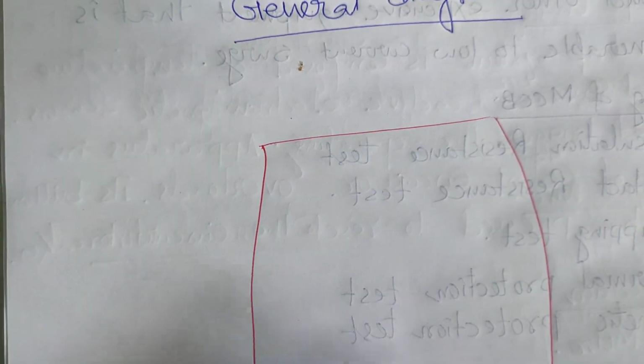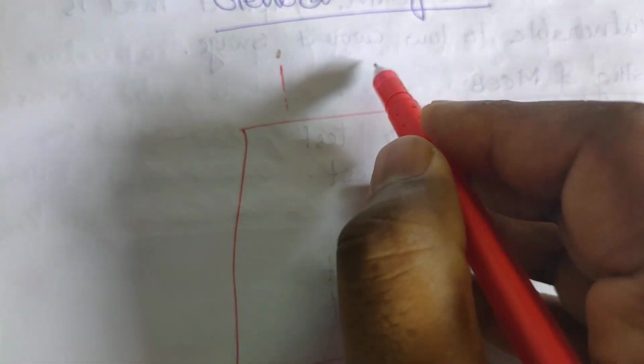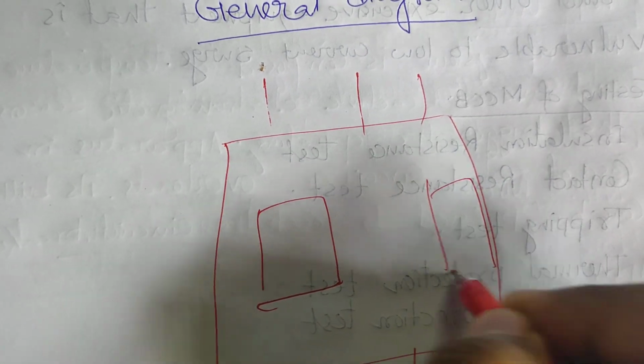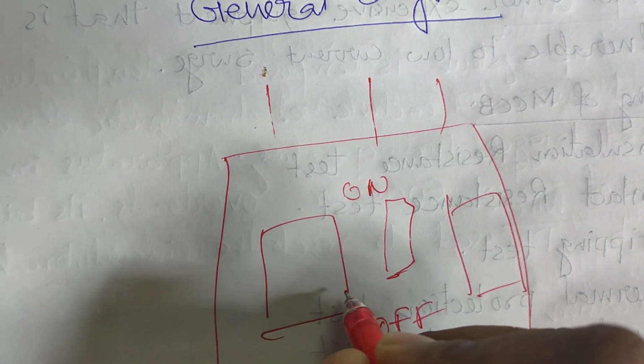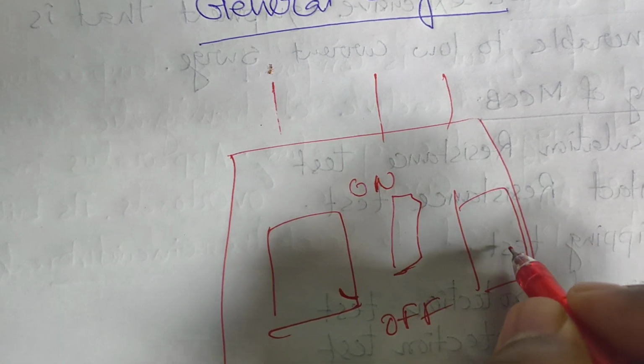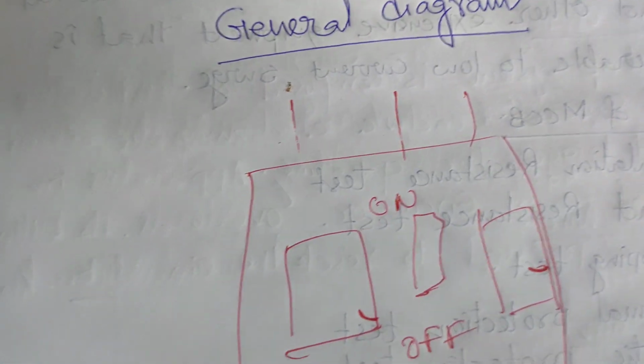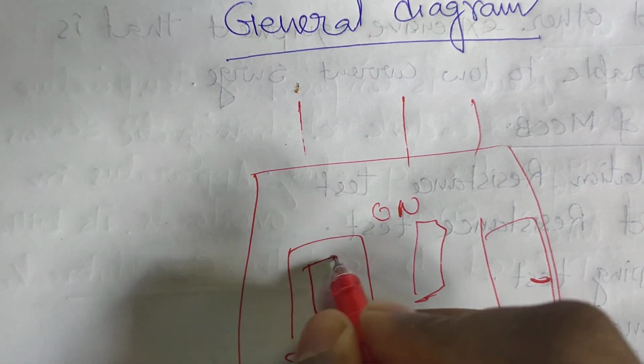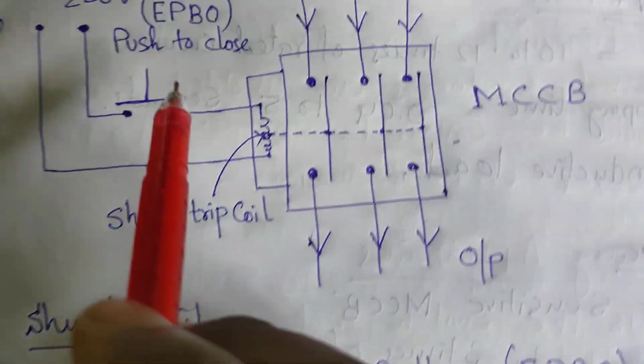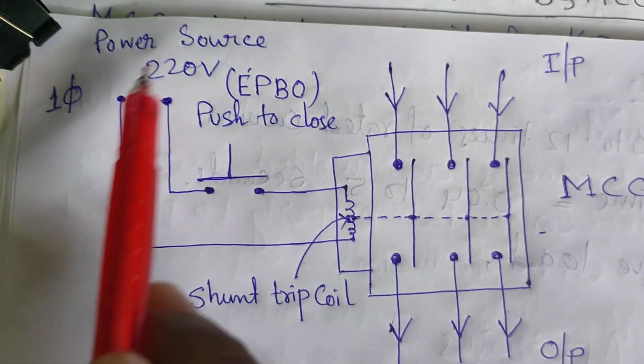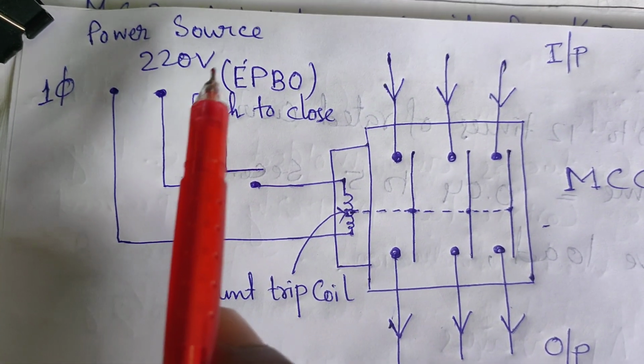Two pockets are there. If this is the MCCB, this is the input, this is the output, and inside all the mechanisms are there. Two pockets are there, one here and the other here. Here is the on/off switch, and this is connected with a mechanical latch. This is also connected to a mechanical latch. We have to place the shunt coil here, and we are drawing the shunt coil diagram. This shunt coil is connected to the 220 volt AC supply, single phase.